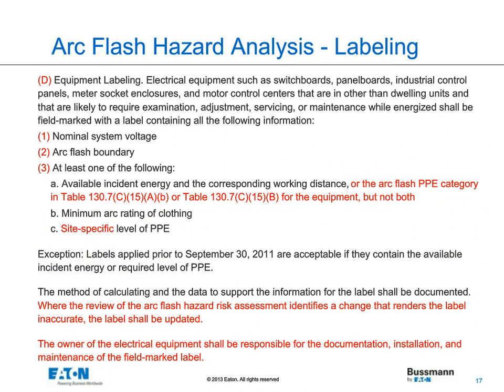My last slide talks about the labeling requirements, and we've done some rearrangement of this section. We first start off with the fact that we have to indicate the system voltage and the boundary. That was also indicated previously, but we moved it up in the list. In item 3, we've enhanced the marking requirement to make it clear that you either mark the incident energy and the corresponding working distance, or the arc flash PPE category, but not both. So you would never mark the incident energy and the PPE HRC category, for instance. This was a common mistake. A lot of labels out there mark both. This says you would mark only one or the other.